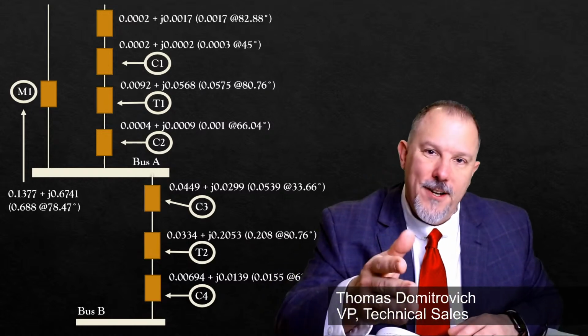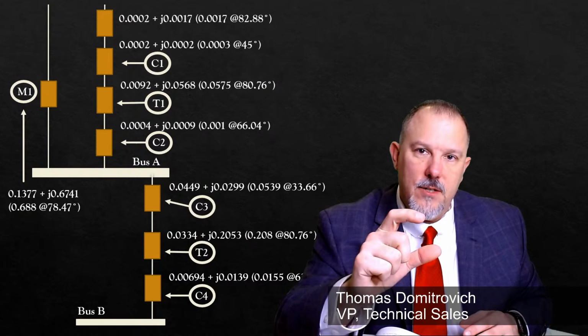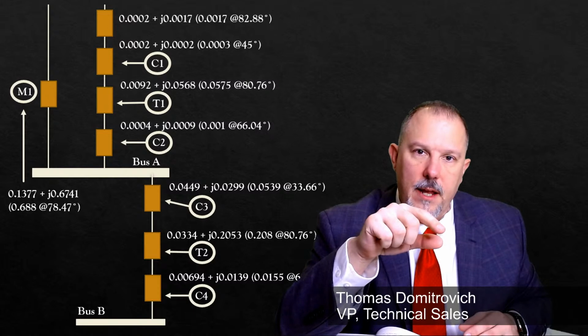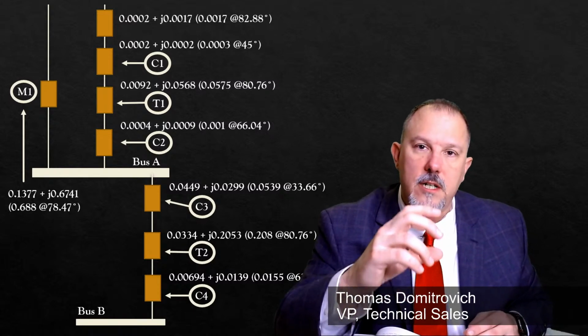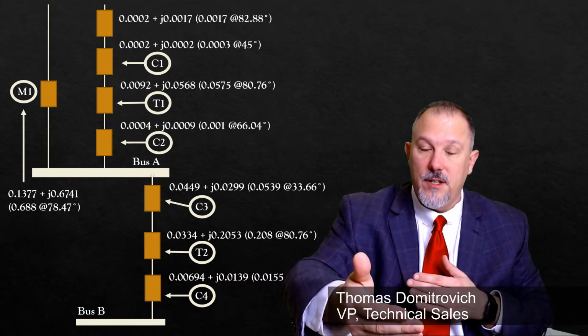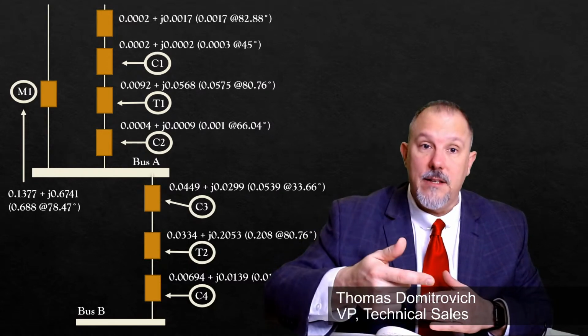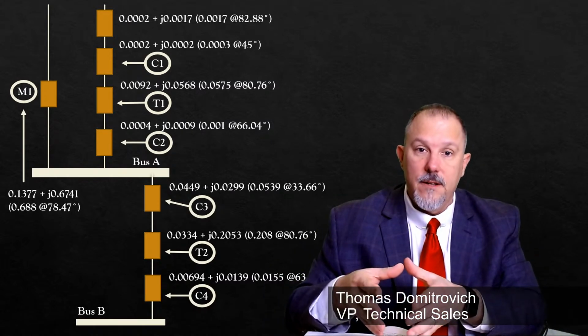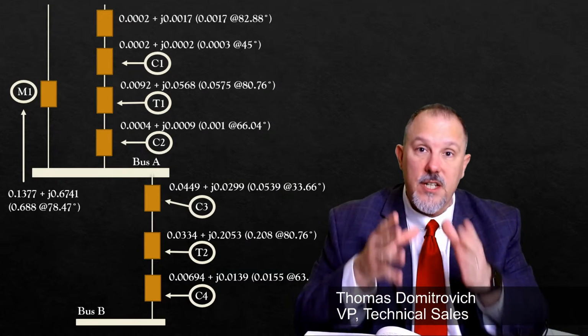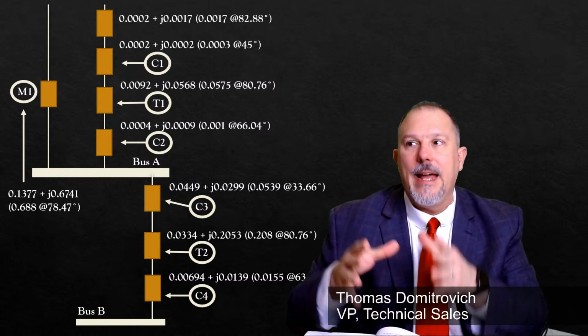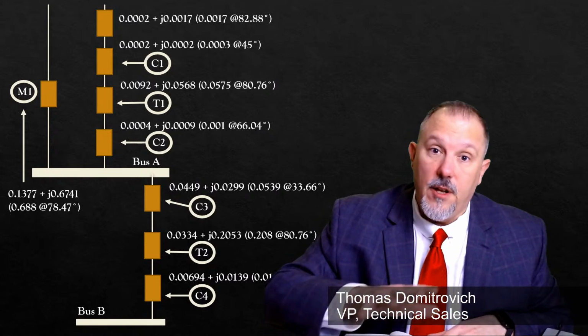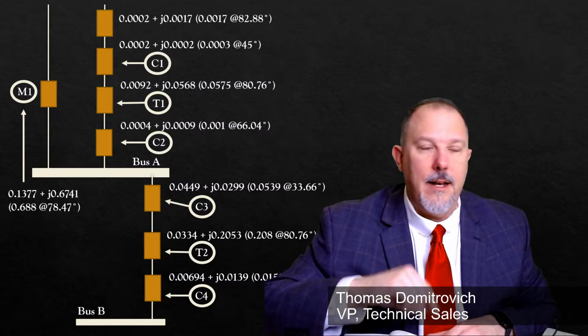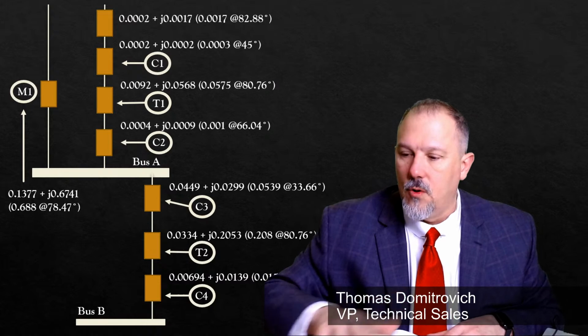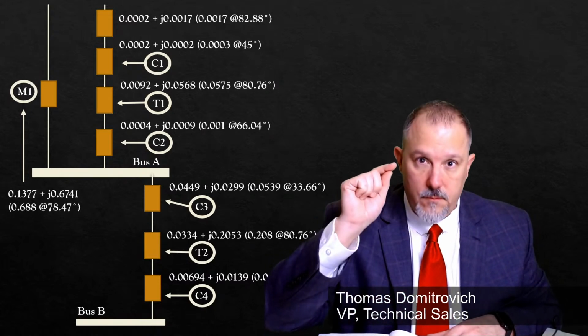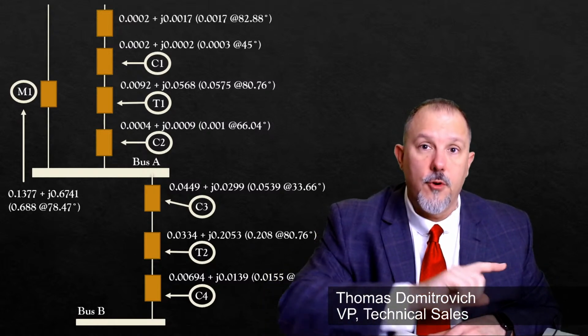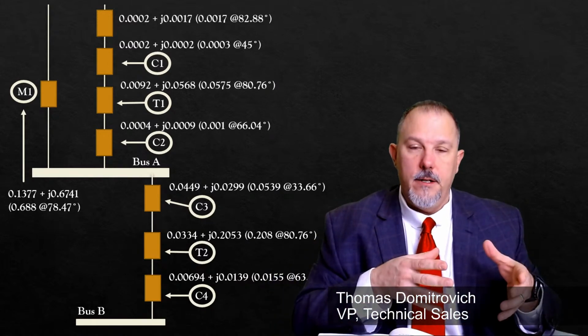But that motor would play a role. A motor has delta windings, right? The core, if you modeled it, would be a delta configuration. So a motor is not going to contribute ground fault, zero sequence. It's going to contribute current, but it's not going to contribute zero sequence. So I would not include the motor in my zero sequence diagram, because zero sequence currents will not flow through a delta. I could probably try to pull together a symmetrical components only discussion to go through the math, but it is really heavy math with a, a squared, and a is the square root of, it just gets heavy real quick.